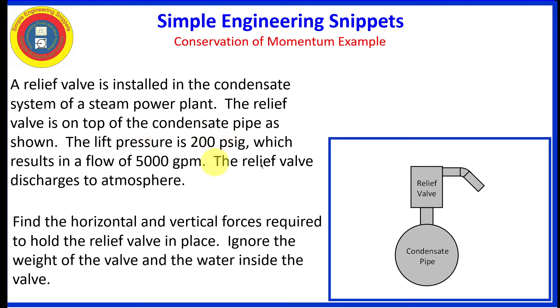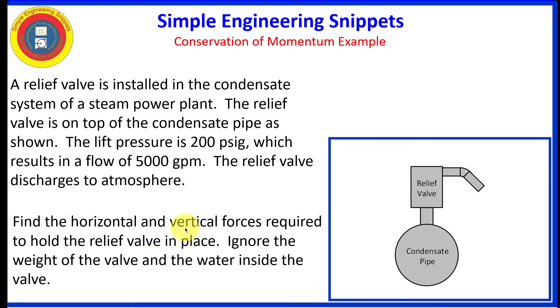Here's the situation. We have a relief valve located on top of the condensate pipe. Its lift pressure is 200 pounds per square inch gauge, and that results in a flow of 5,000 gallons per minute. The relief valve is relieving to atmosphere. Our goal is to determine the horizontal and vertical forces required to hold the relief valve in place, and we are going to be ignoring the weight of the valve and the water inside of the valve.